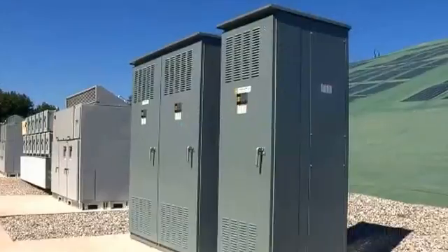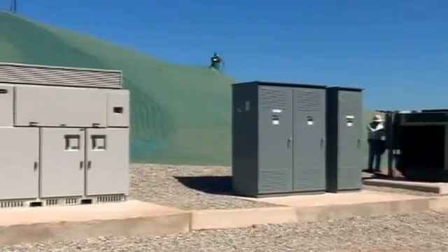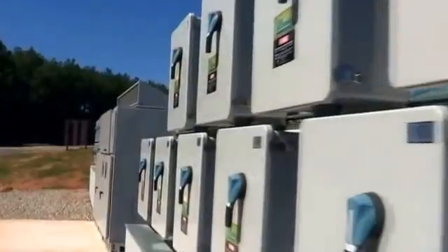Each of these solar arrays is roughly 250 kW. That matches with each inverter. So you have 4 inverters rated for 260 kW. The system overall is operating at 1 megawatt in total. That will be equivalent to producing energy for about 224 homes according to the EPA calculator.